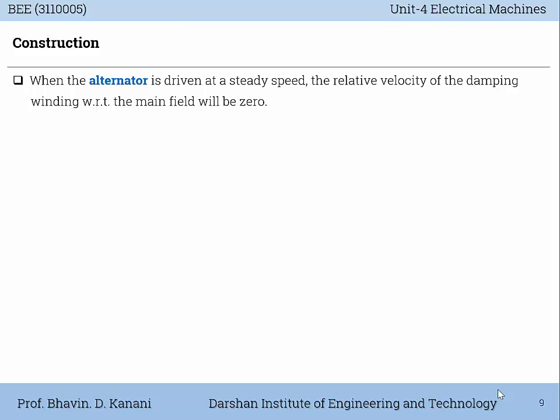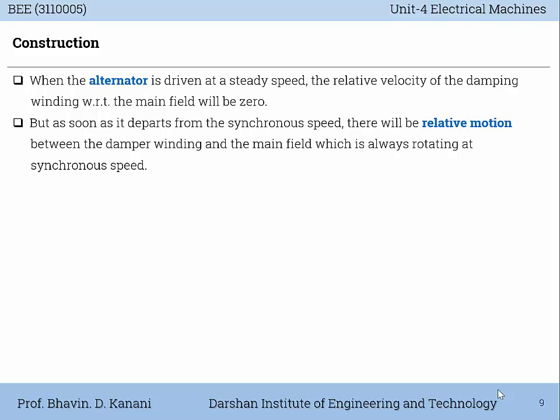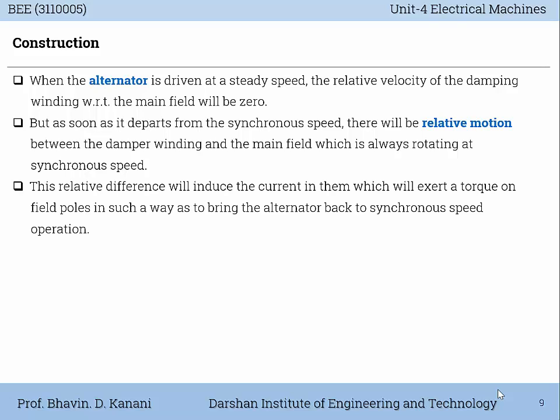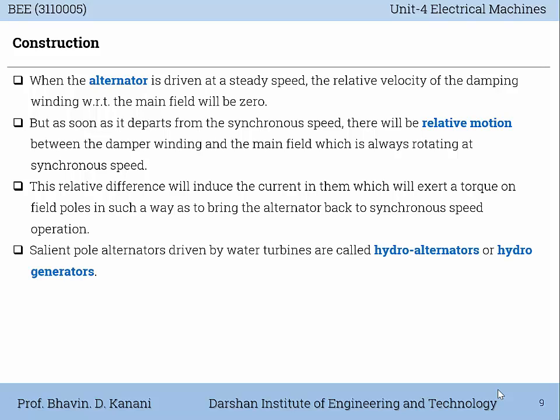When the alternator is driven at a steady speed, the relative velocity of the damper winding with respect to the main field will be zero. But as soon as it departs from synchronous speed, there will be relative motion between the damper winding and the main field, which is always rotating at synchronous speed. This relative difference will induce current in the damper winding, which will exert a torque on the field poles in such a way as to bring the alternator back to synchronous speed operation. Salient pole alternators driven by water turbines are called hydro alternators or hydro generators.